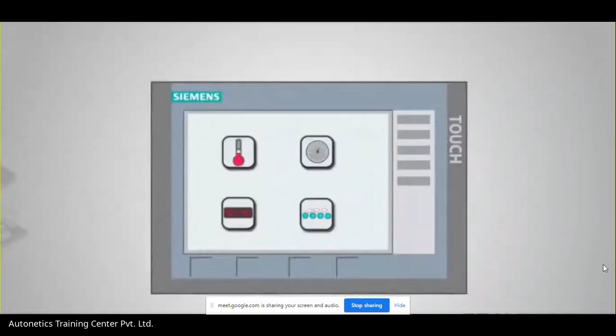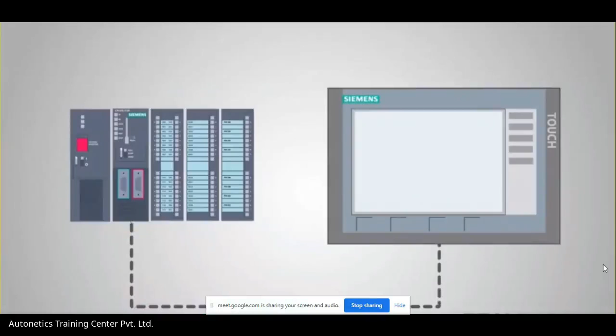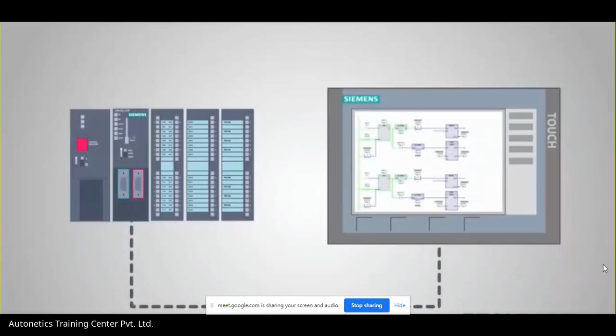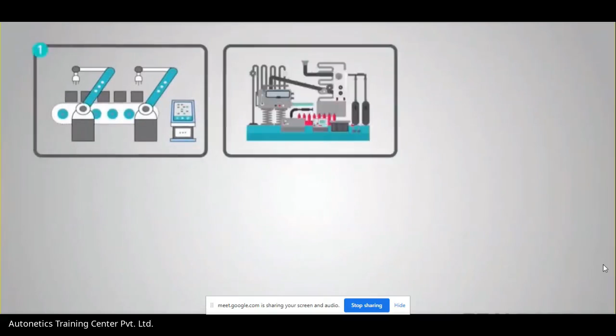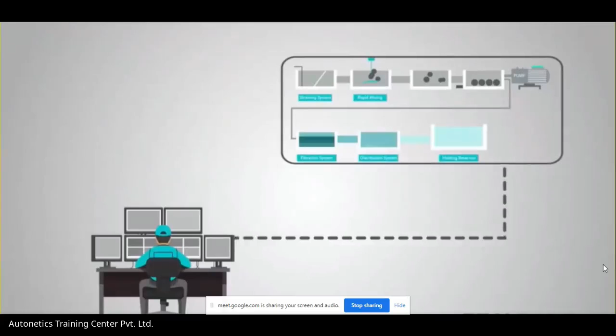The possibilities are only limited by the software and hardware used. For maintenance personnel, many HMIs can also connect to the PLC logic and display it on the screen for troubleshooting purposes, which can save valuable time compared to connecting a computer or laptop every time. Another benefit of having a modern HMI is that plants and other industrial sites can monitor and control multiple machines or other equipment. A small manufacturing facility can even monitor the entire plant from one centrally located HMI. Water and wastewater facilities have utilized this for years by coupling an HMI with a PLC.